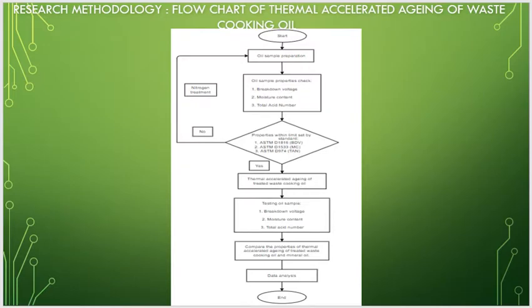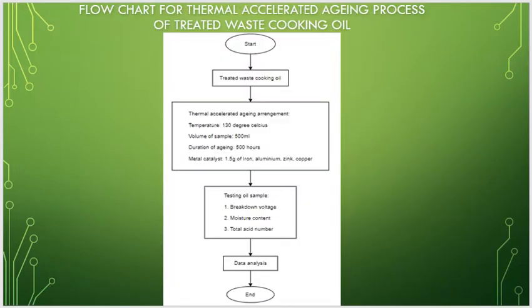Next, for the research methodology, this is a flowchart of thermal accelerated aging of waste cooking oil. This is an overall flowchart, from the oil sample properties check, comparing properties with limits set by the standard, and thermostatic aging of the treated waste cooking oil, then testing the oil sample after the aging and comparing the properties after thermostatic aging between the waste cooking oil and the mineral oil, then data analysis and end. Next, this is a flowchart for the thermostatic aging process with the treated waste cooking oil and the characteristics for the thermostatic aging arrangement: temperature, volume of sample, duration of aging, and metal catalyst. Then testing the oil sample after the aging and data analysis.